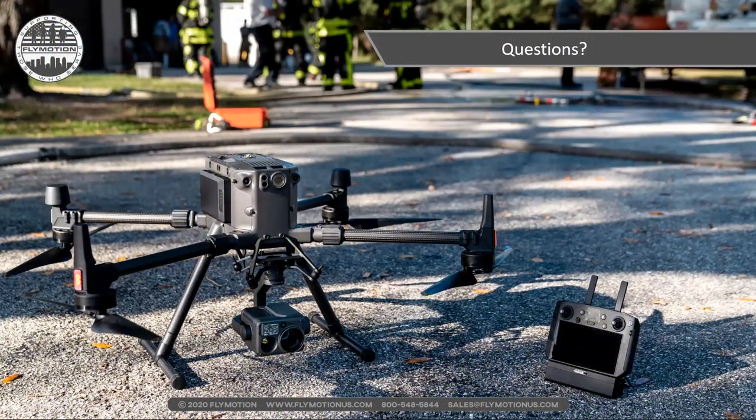And if you are flying with gas detectors, one thing I will say is remember you're limited. The drones fly very fast, and detectors sniff really slow. So whenever you're surveying an area, you need to be in one location for a period of time to allow your sensors to pick up and sniff the area, and then move on to the next. Just as you would with any regular handheld gas detection, with a firefighter walking through a room, just use your same old sampling techniques.